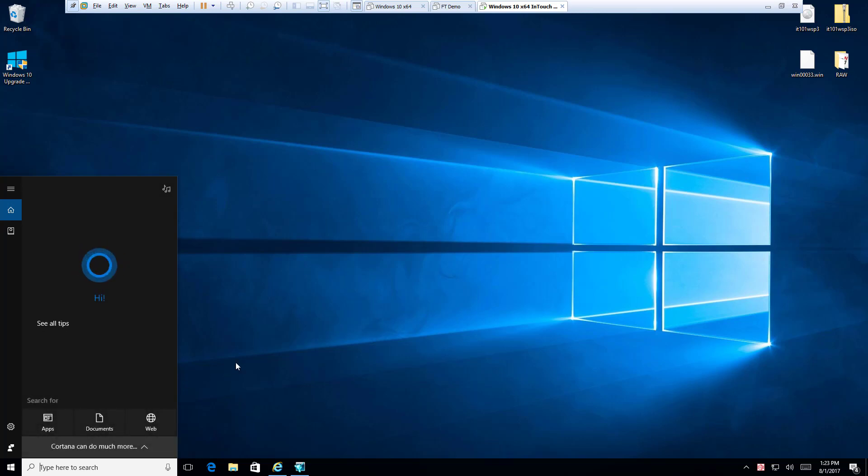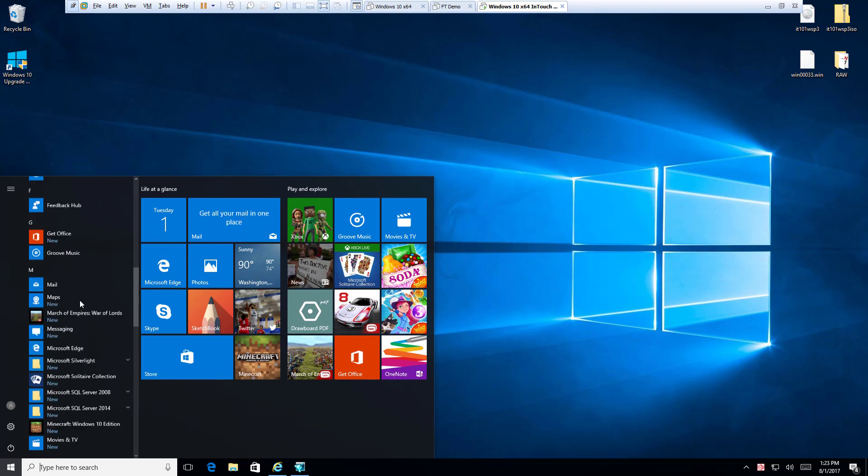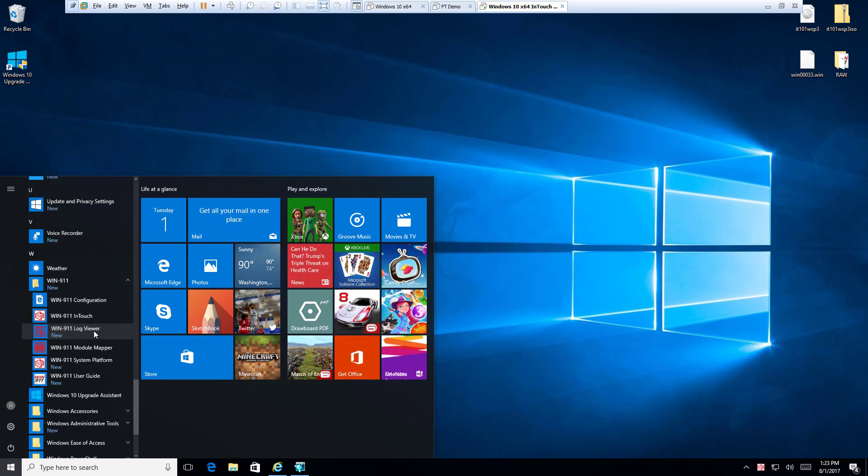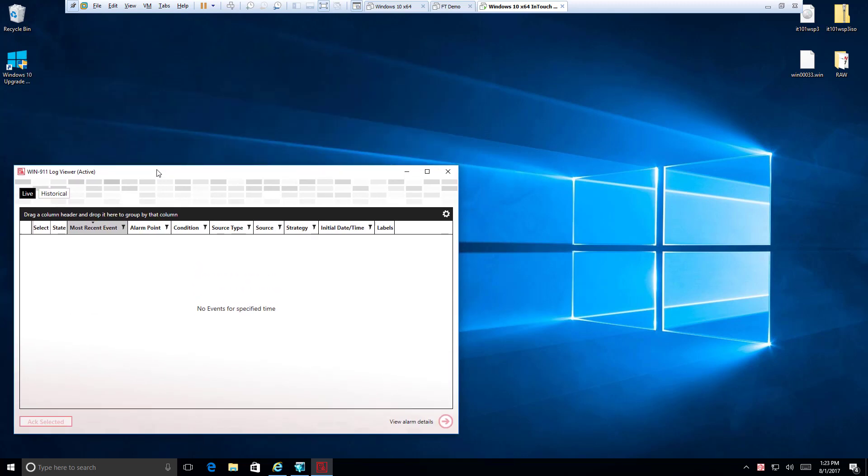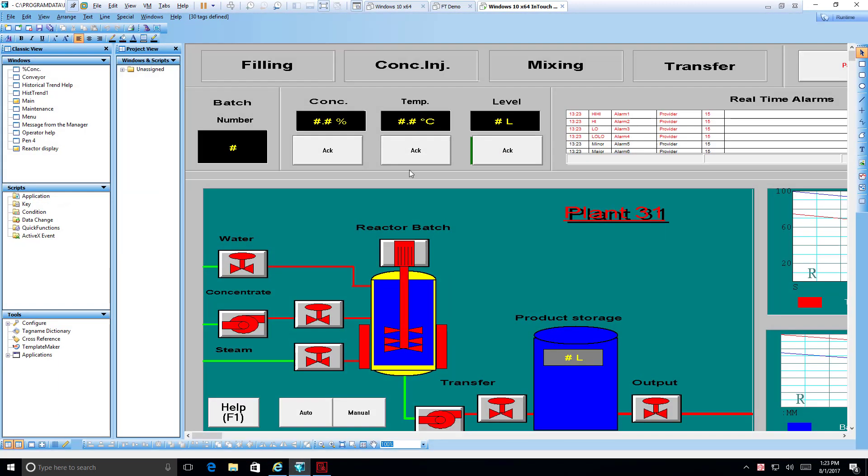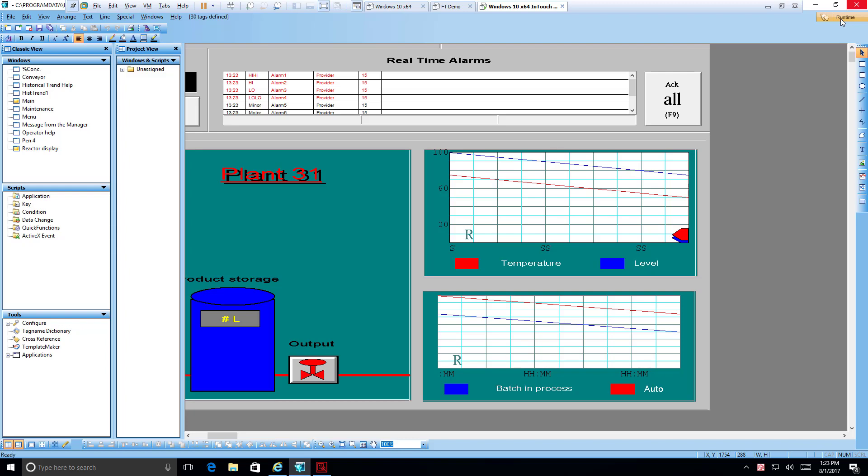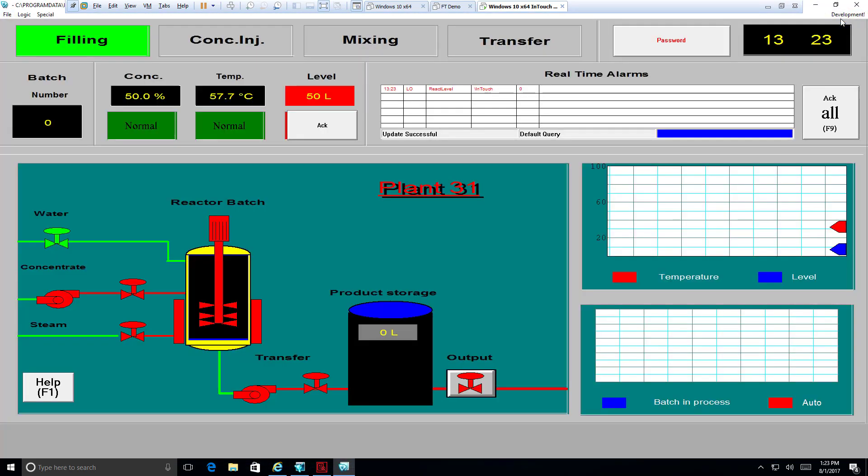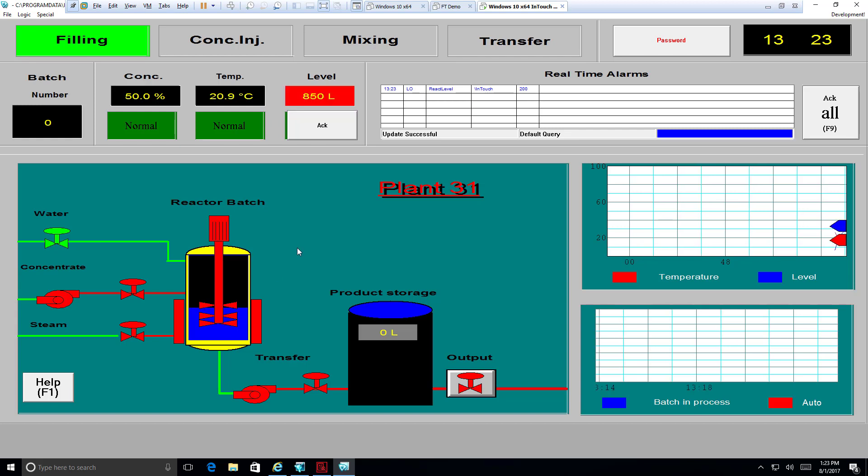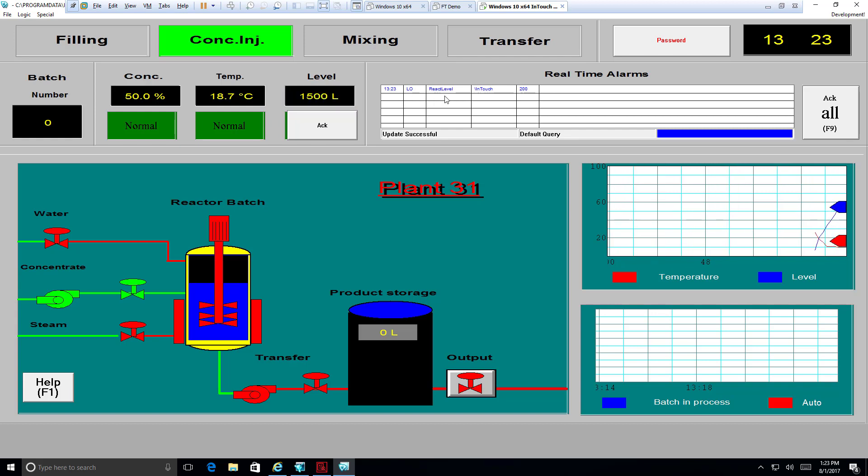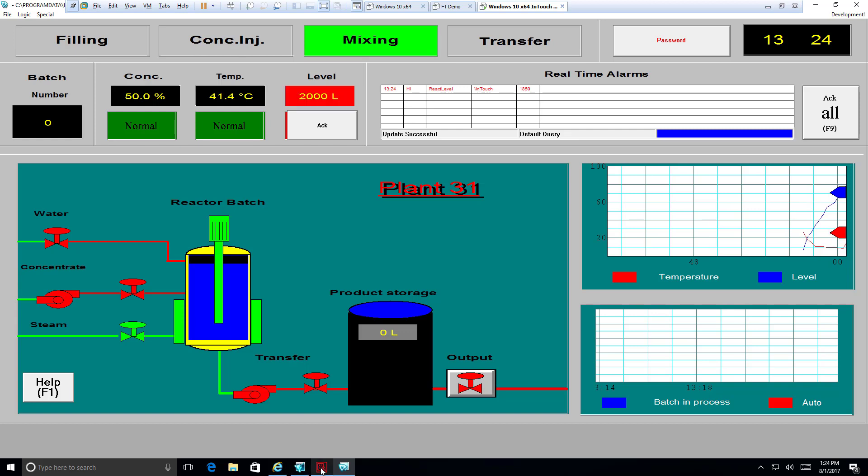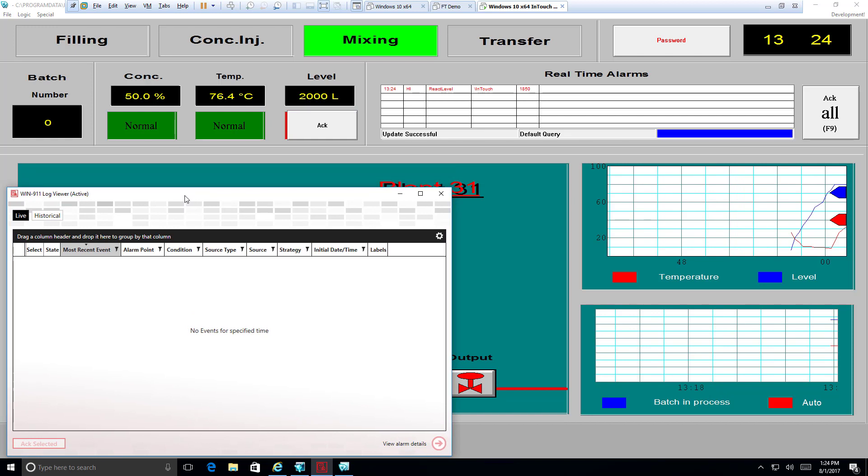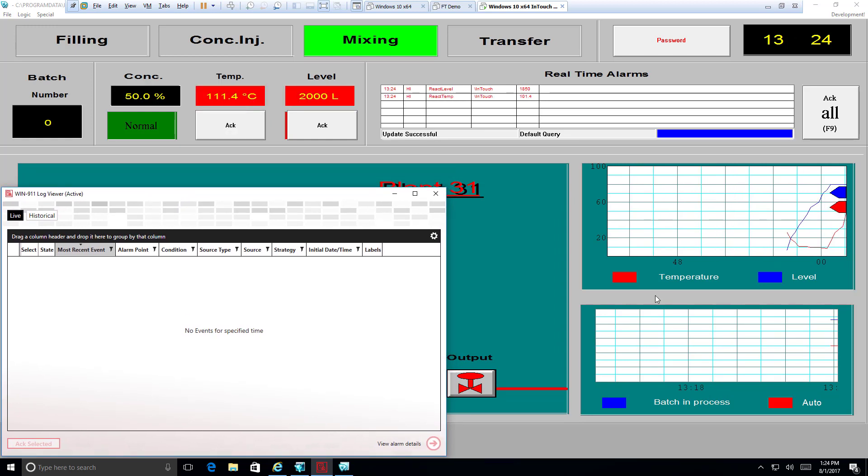Lastly, since we don't have anyone to receive these notifications, we can use our trusty Win911 log viewer. And this allows us to see basically the status of the system and any alarms going on at the moment. So we'll start this up and have it ready to start displaying what alarms are happening. Go back to our in-touch app. This preset demo app is very nice and all you have to do is hit run time. And it should open right up. And alarms should start being triggered. As you'll see right here, we have a level alarm for our reactor. And it was started at the low level. As you can see it was below 200 and pretty soon it's going to rise, rise, rise above to the high level. And that should trigger an alarm for us. Temperature will get there soon as well. Here we go. We see that there's an alarm triggered in in-touch. Now we just need to make sure that in our log viewer that alarm comes through as well. And we'll just give it a second to travel over the network.